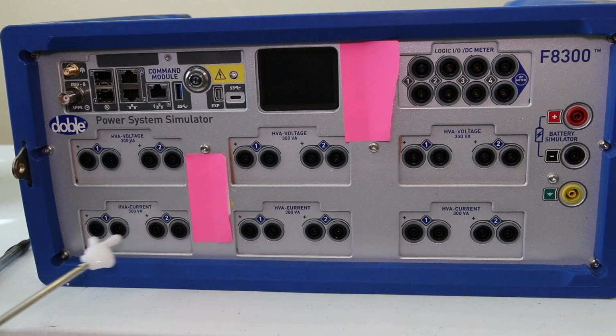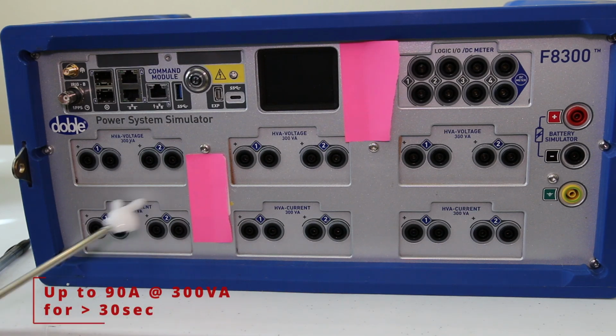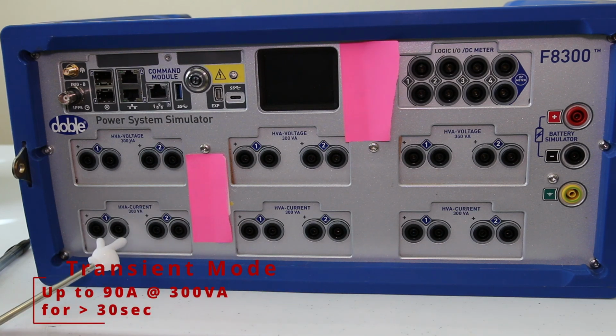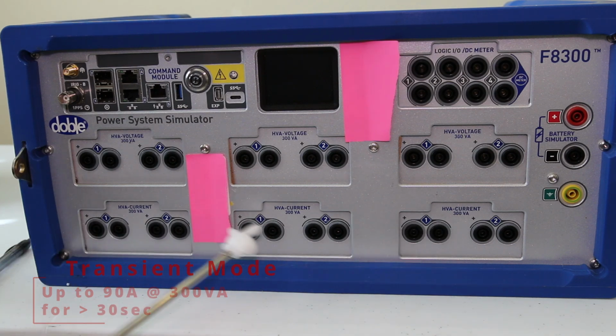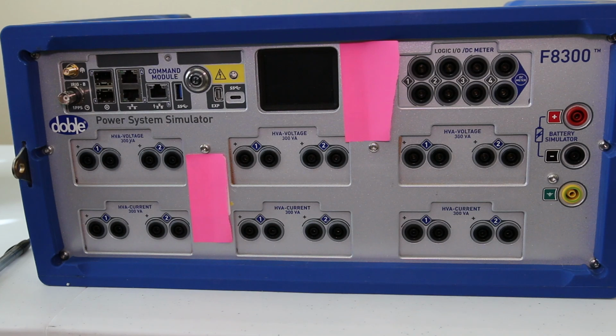In transient mode, this is where the real improvement is. Each module will run 90 amps at 300 VA for 30 seconds, which is incredible — that's a lot of power we're getting out of here. And each module can also run 50 amps in DC output mode.